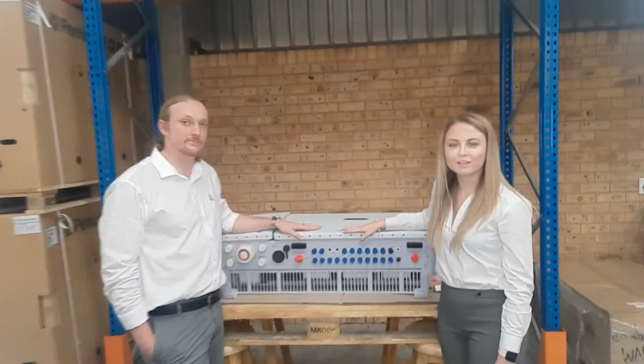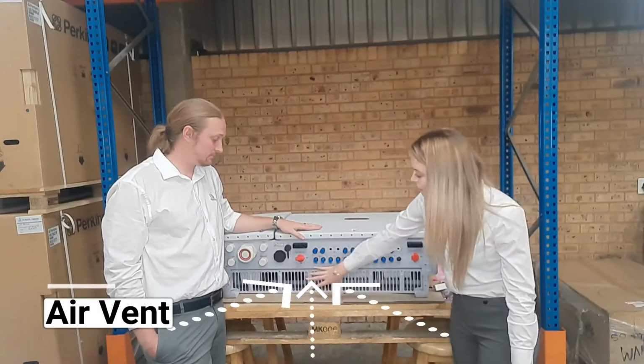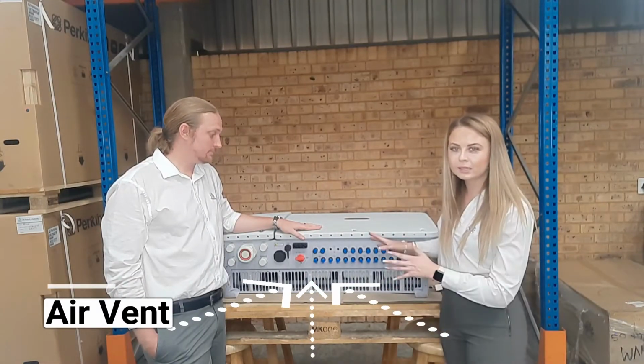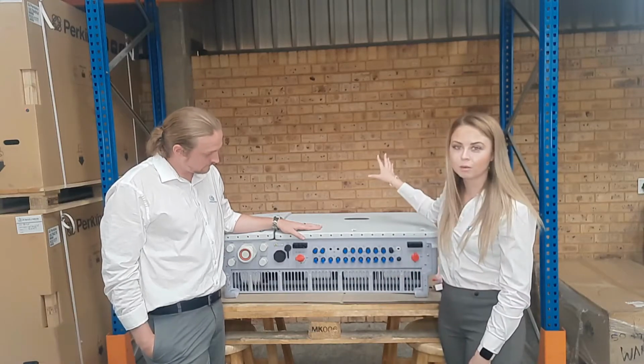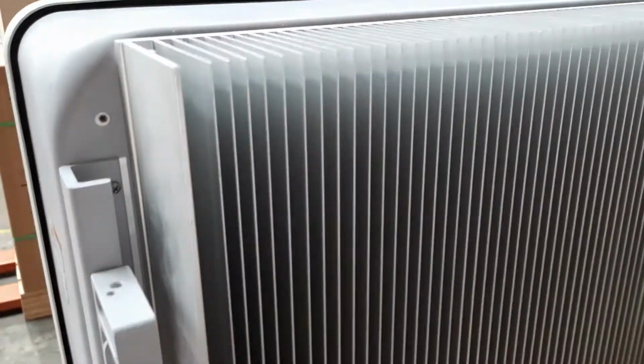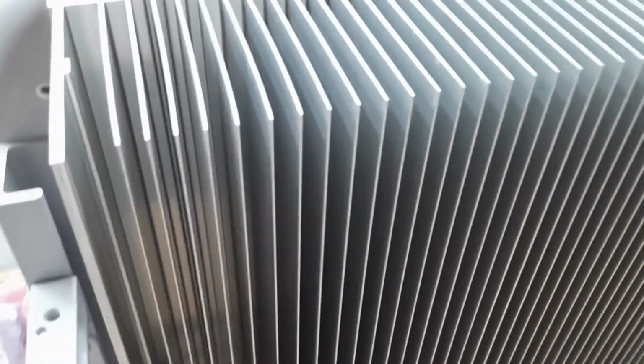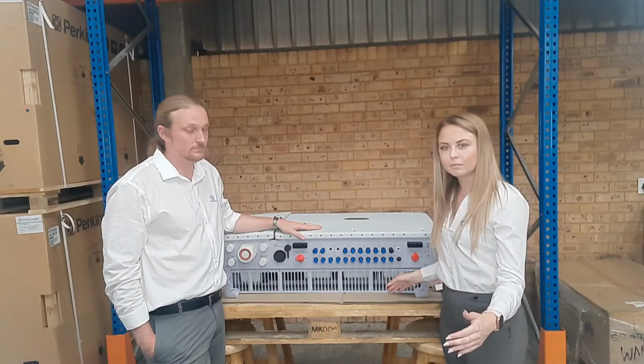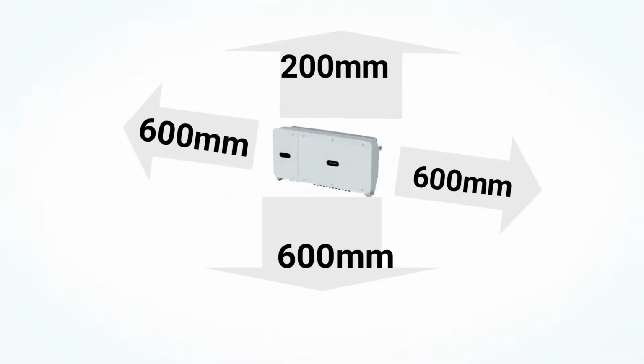So now we're looking at the bottom of the inverter. Here you can see the air vent where cool air will enter and the hot air will be removed from the top. This inverter uses fanless natural cooling. The heat sink on the back is very effective at keeping the inverter at the right temperature. We recommend at least 600 millimeters of clearance for it to be able to work properly.